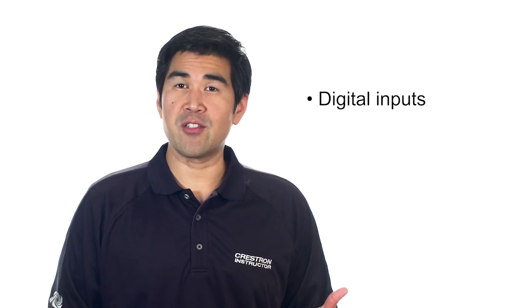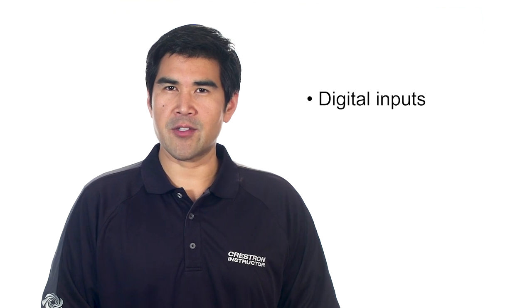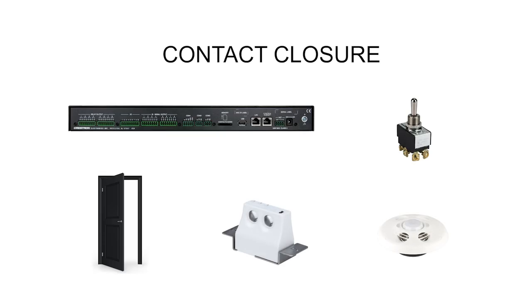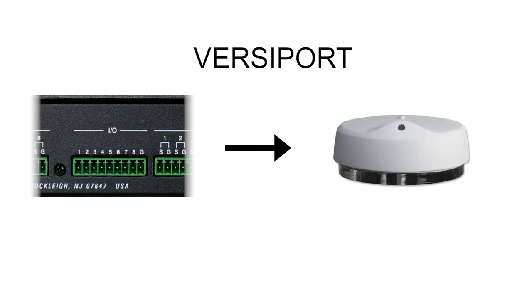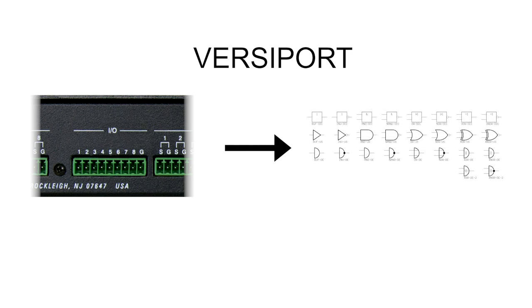Control processors also have digital inputs, and there are two types depending on the processor. The first type is a basic digital input — using the contact closure input allows the processor to be aware if something has changed, such as a door contact in a partitioned room or a motion sensor. The second type is the Versiport. The Versiport does everything a normal digital input can do, as well as being able to read an analog voltage between 0 to 10 volts DC, usable with third-party sensors such as a temperature sensor or photocell. The Versiport can also act as a TTL, or Transistor-Transistor Logic Switch, which is sensitive to voltage changes and common in industrial controls.